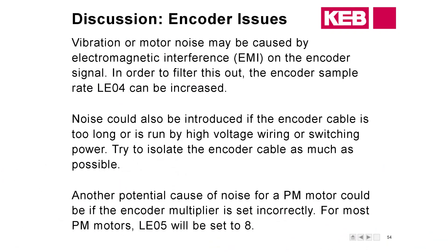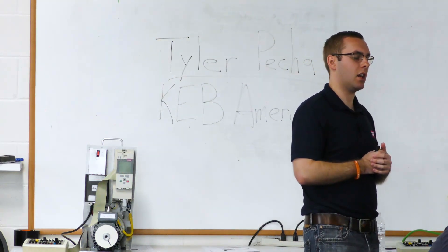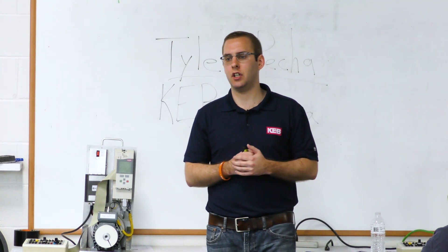One other note: LE05 is also the encoder resolution number. That's going to be set to eight as a default for NDAT applications, and two as default for TTL. If that is set to a different value for some reason, it could also cause noise. But if you select a permanent magnet or induction configuration, that should automatically be set correctly.